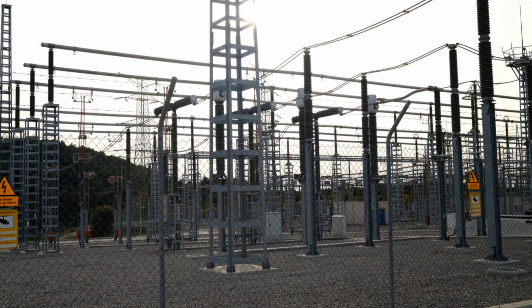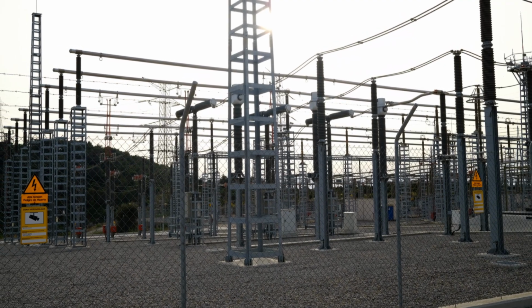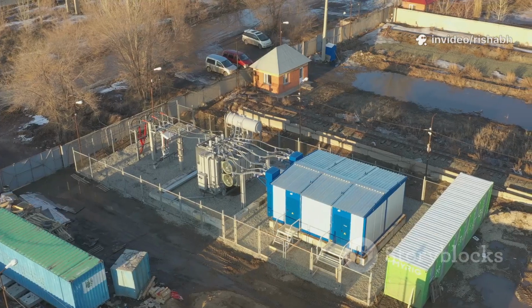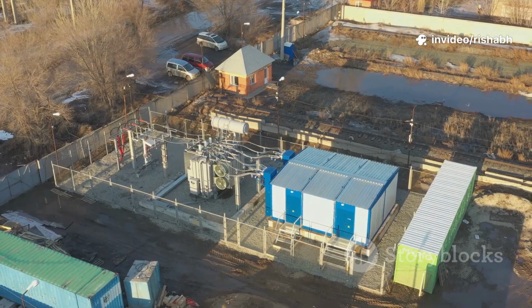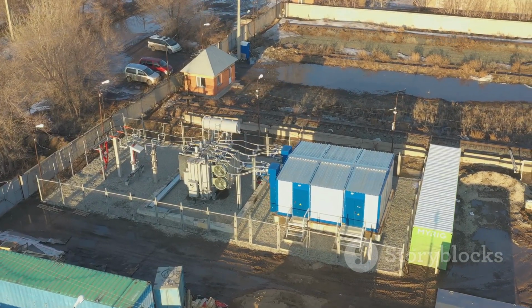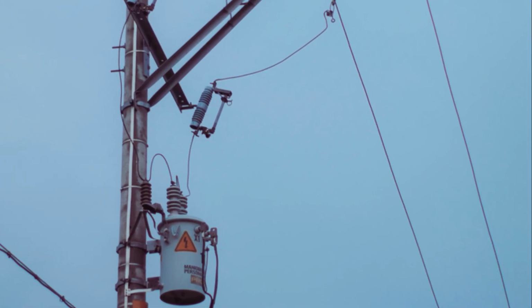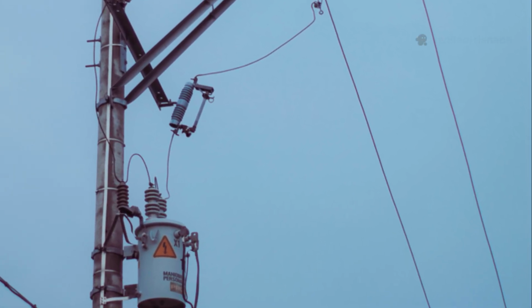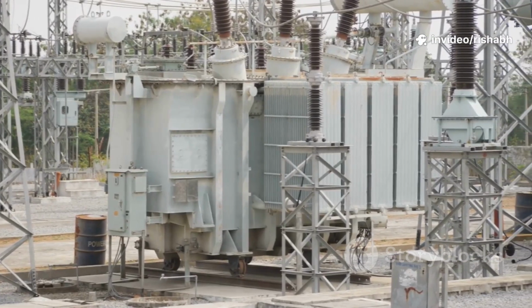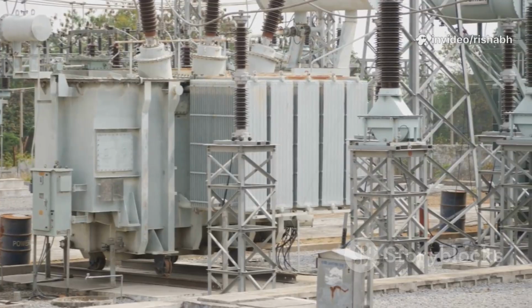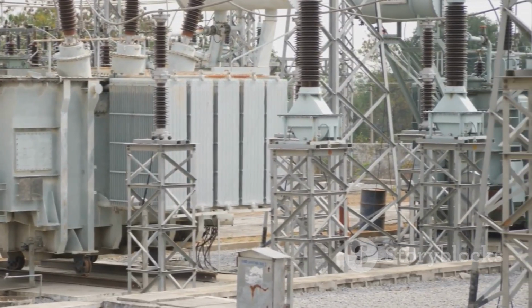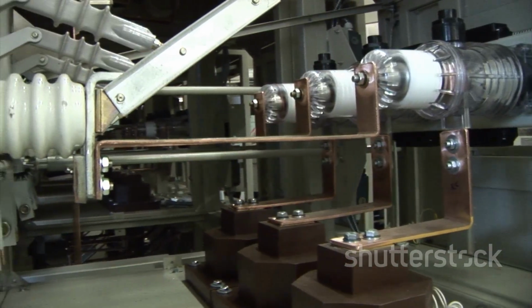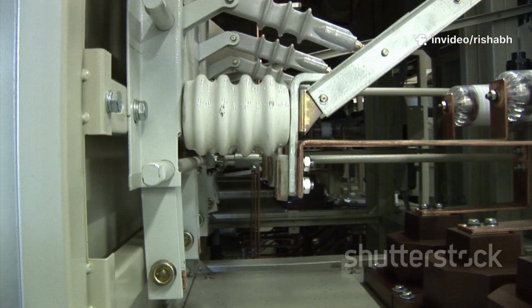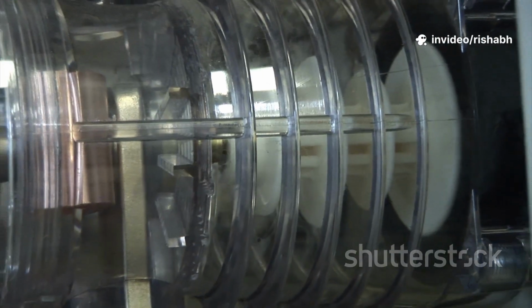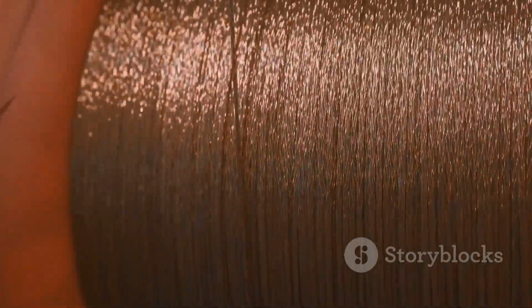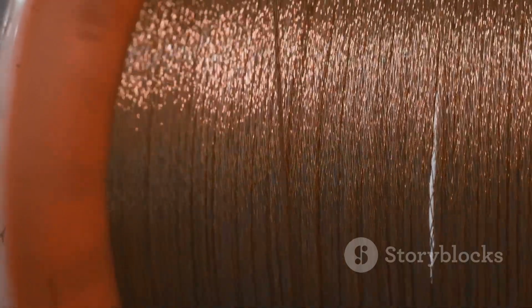The size of these transformers, measured in megavolt amperes, reflects the amount of power they handle. A massive 500 MVA unit in a transmission substation is a galactic center of energy, while a small pole-mounted transformer is like a local star serving just a few homes. The basic construction of these giants is elegantly simple, rooted in Michael Faraday's discovery of electromagnetic induction. At its core, literally, it consists of two or more coils of insulated wire, called windings, wrapped around a shared magnetic iron core. There are no moving parts in the basic transformer, a beautiful example of physics in action.